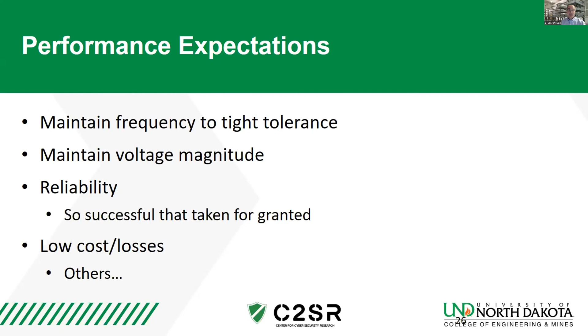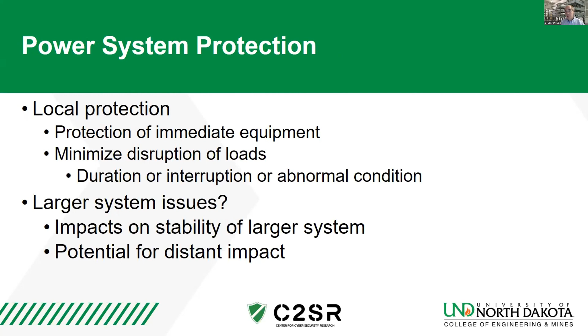The other thing is trying to keep the cost as low as possible, which also often means keeping losses low. Part of maintaining that reliability is power system protection. This is detecting short circuits in equipment and responding to them, isolating as little of the system as possible, and also trying to keep the interruption as short as possible. Now, this is one of the areas where human error comes in. Anytime there's a protection operation on the bulk power system, utilities are expected to evaluate it and see, was this a correct operation? And there's still a surprising number of these that are due to incorrect settings. And in a few cases, these settings errors have led to cascading outages.